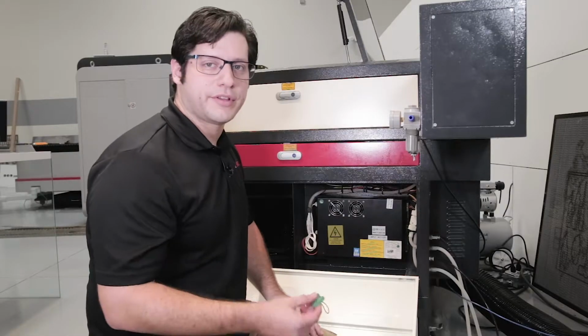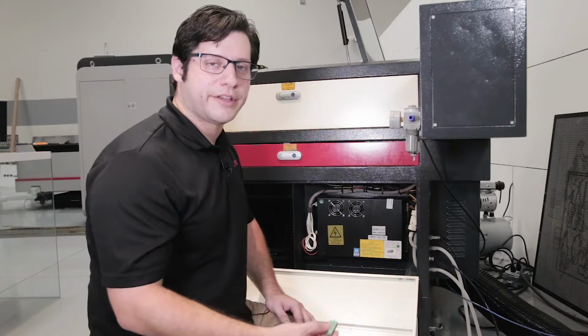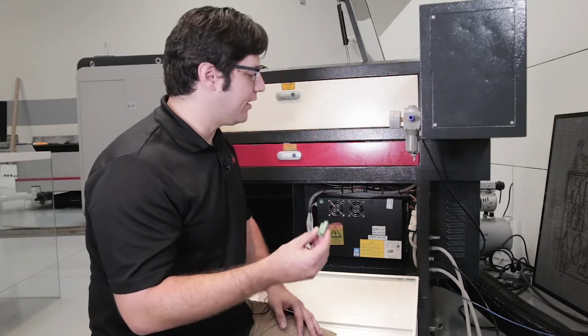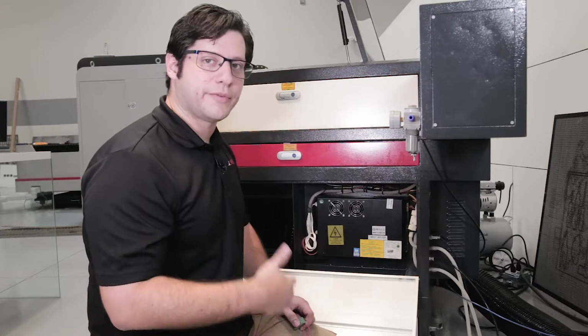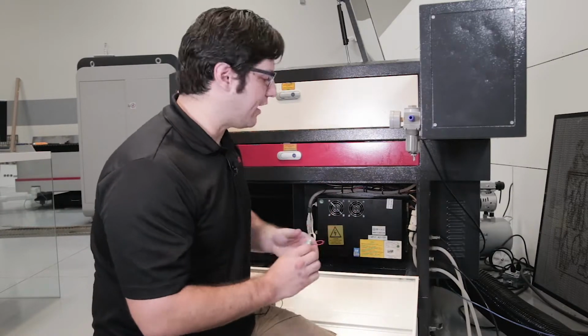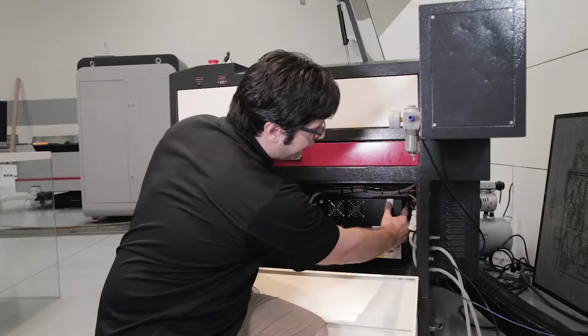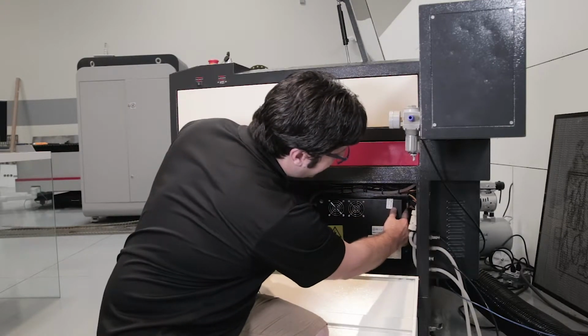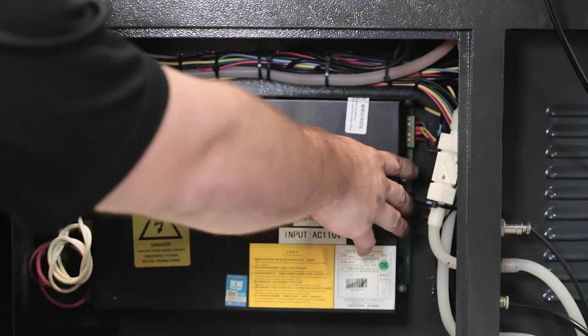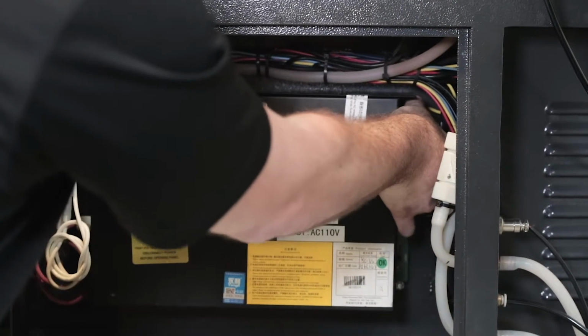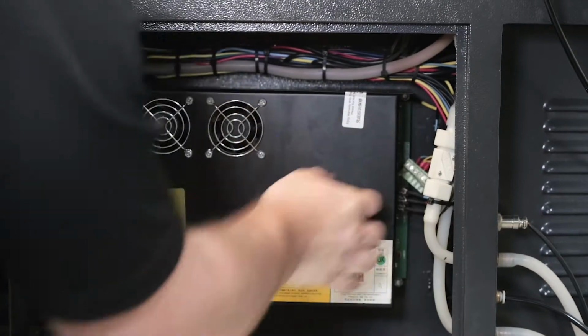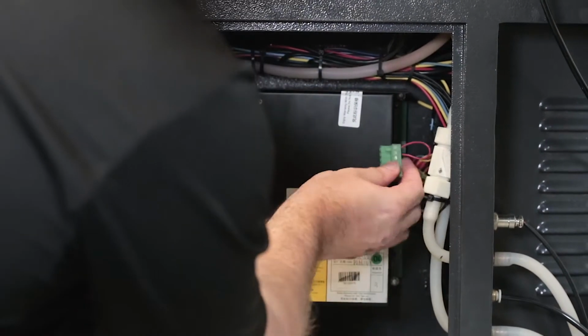From here, we're going to go into checking if the laser actually fires without having the control panel or interlock system connected. So we're going to use the 6-pin bypass next. So next we're going to check if the power supply is actually firing. So we're going to need the 6-pin connector, and you're going to make sure that you have the machine off when you disconnect this connection at the power supply. It's going to be right here. You'll notice there's about 4 connections here, and then it's a 6-pin just like the bypass. You'll go ahead and unplug it, and then go ahead and put in your bypass.